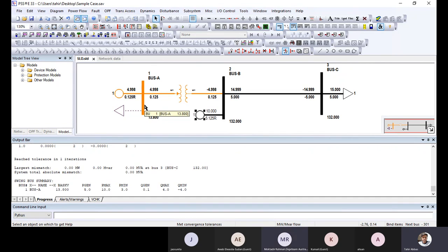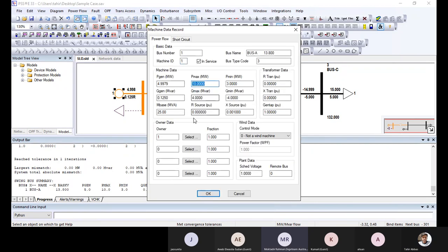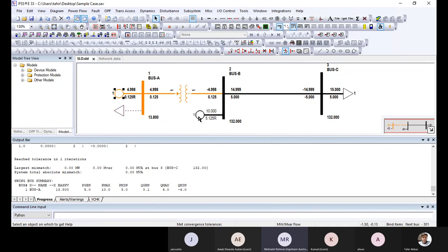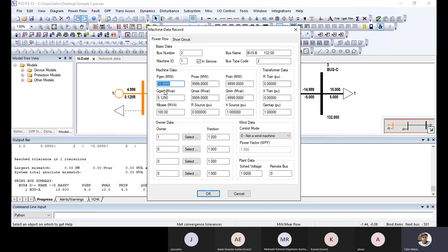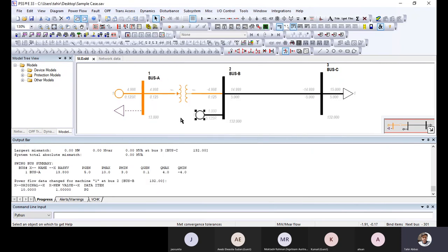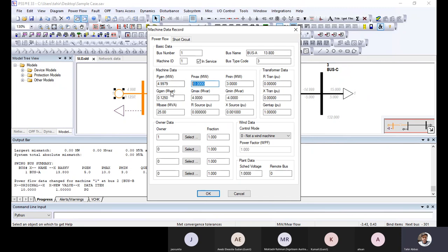So similarly, you define the swing generator max capacity as 10 megawatt, right? But it went up to 13 megawatt. That means you're overloading the swing generator. Yes, basically, because there is no other generation. Now you can see that I have added 10 here. The demand is 15, I'm making it 14, so now 14 megawatt is required and I have added 10 megawatt Pmax. Practically it does not go beyond this value, but this is a swing. The name defines that it is flexible.